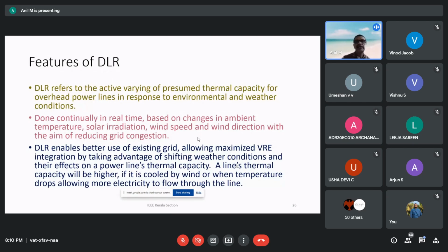DLR is done continually in real time. The monitoring is done continually in real time based on changes in ambient temperature, solar irradiation, wind speed, and wind direction, with the aim of reducing grid congestion. DLR enables better use of the existing grid, allowing maximized VRE integration by taking advantage of shifting weather conditions and their effects on a power line's thermal capacity. A line's thermal capacity will be higher if it is cooled by wind or when temperature drops, allowing more electricity to flow through the line.